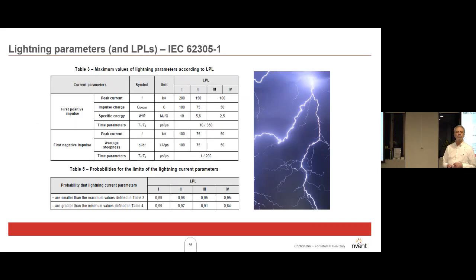Here is a table from IEC 62305 telling you what surge current you can expect on a site. If we look at the top right system cell, under the lightning protection level 3 heading, you'll see that it suggests a peak current of 100,000 amps will hit your structure. That's the 10-350 microsecond waveform.